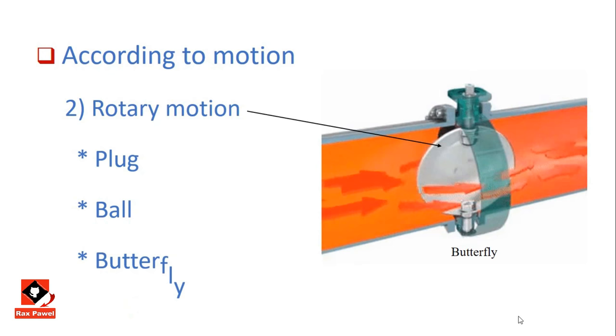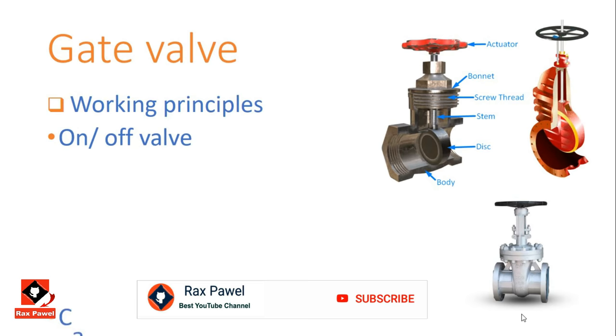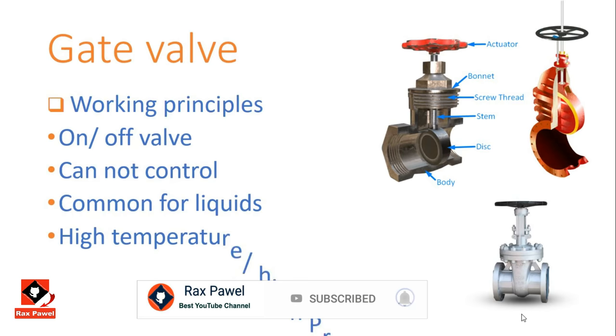Gate valve working principles: it applies only for on/off applications, moved by a stem perpendicular to the direction of flow, and it cannot regulate or control the flow. It is commonly used for liquids and is suitable for high temperature and high pressure applications.